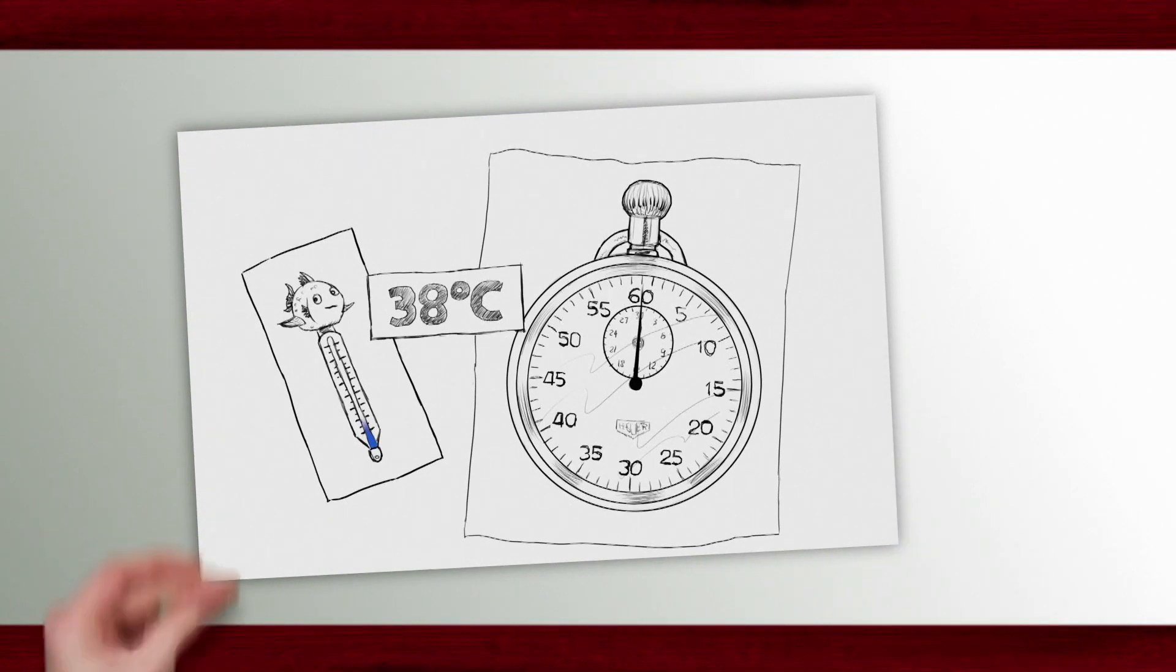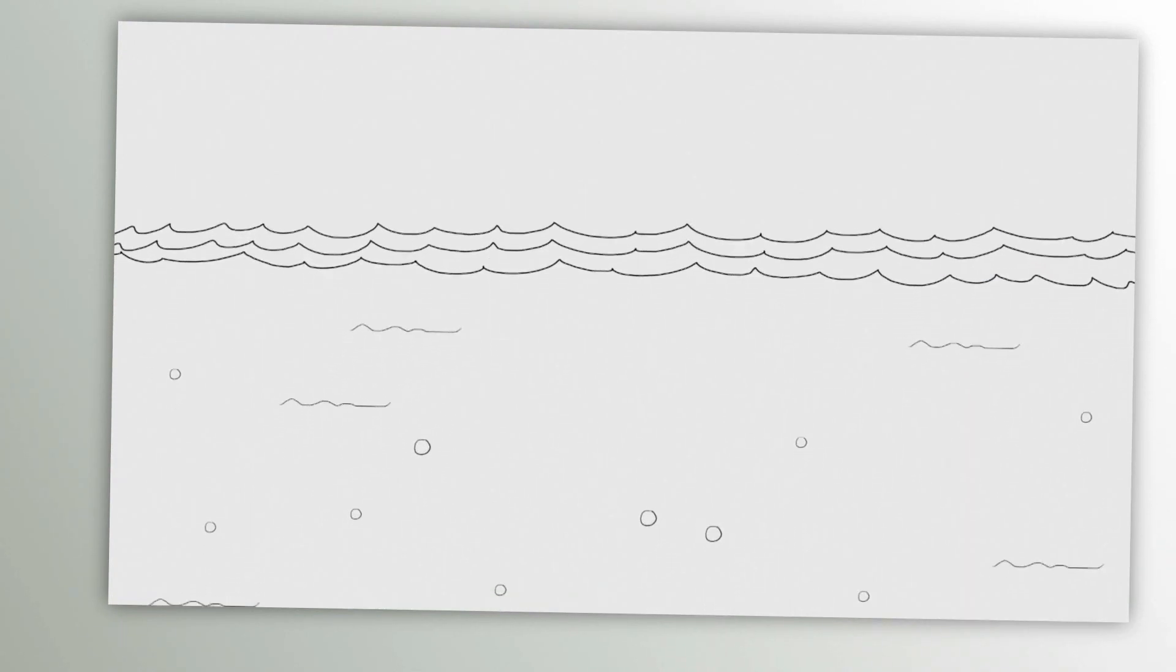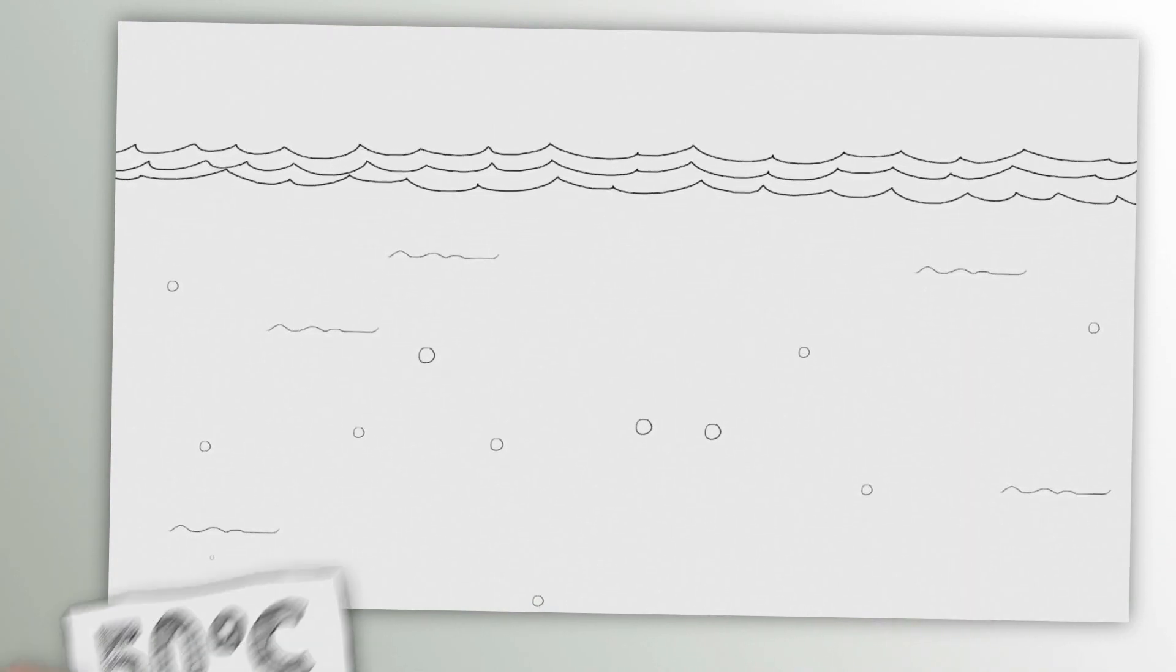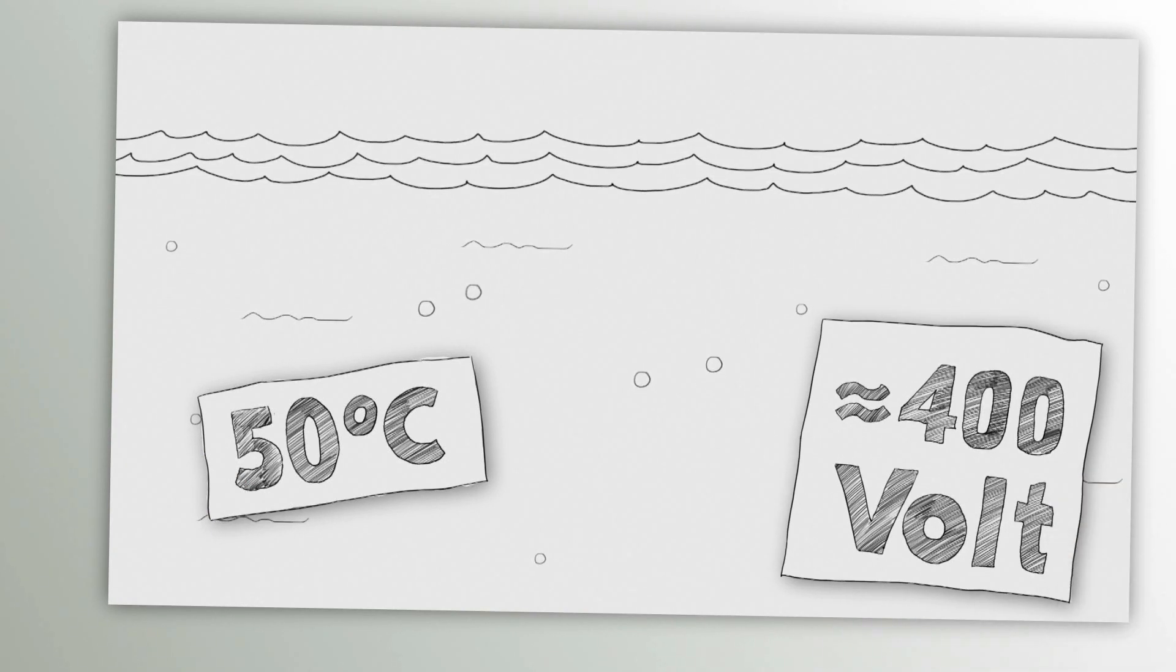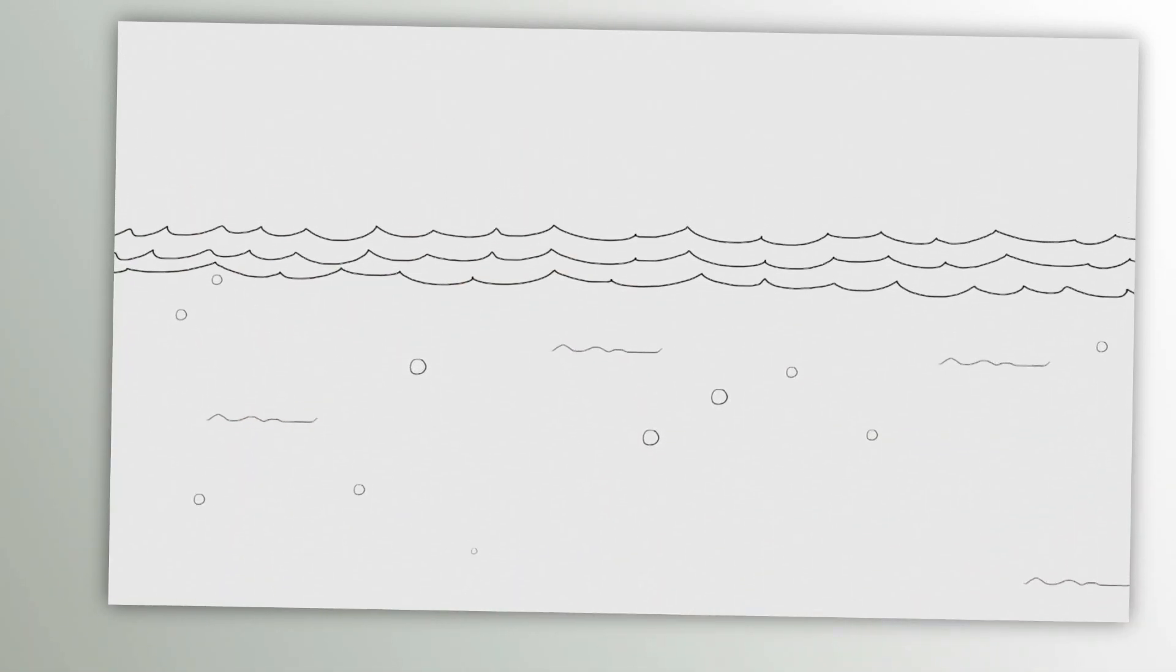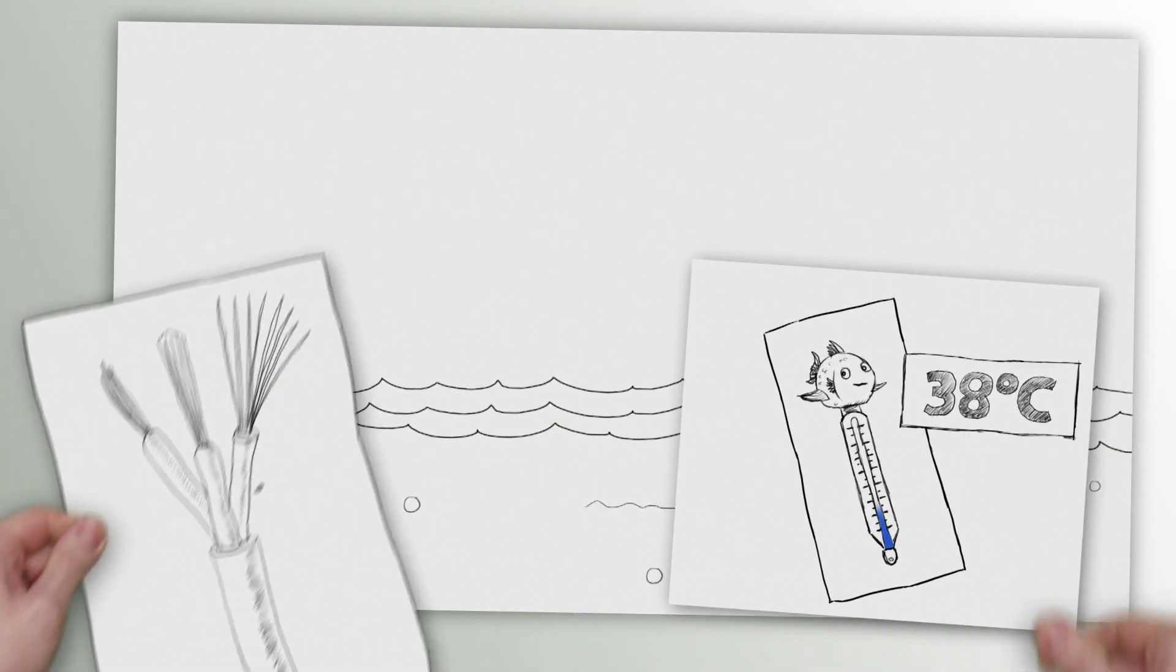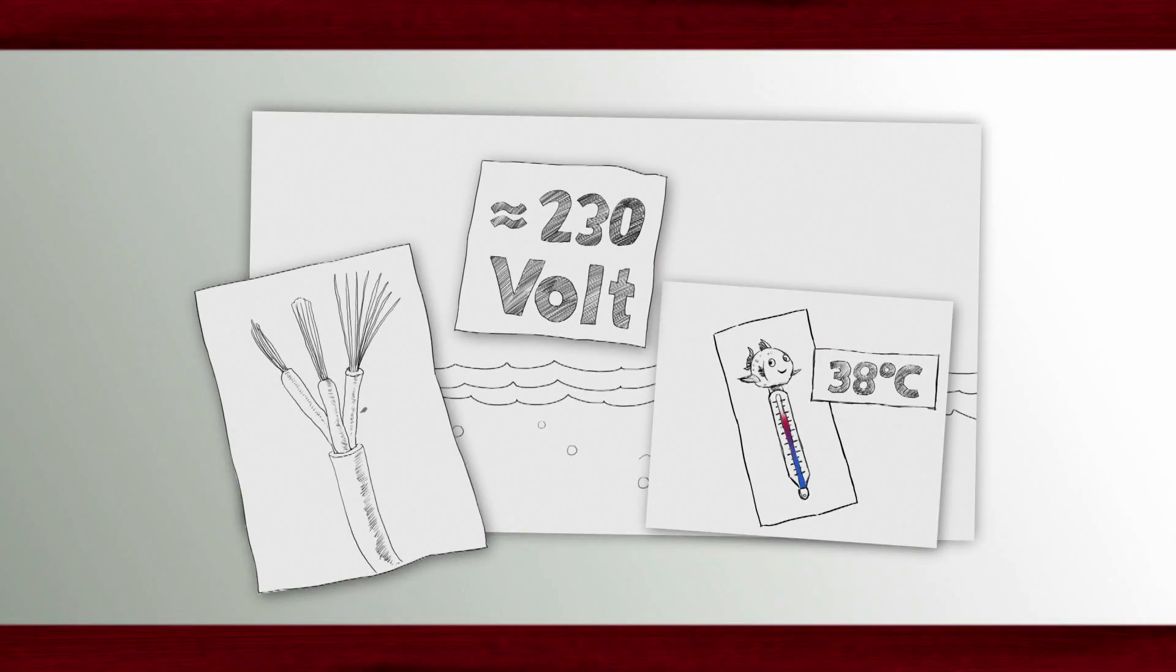Since instantaneous water heaters are based on the principle of heating water to the required temperature very quickly, these appliances need a lot of power for a short period of time. This is logical and explains why, when they have to produce large amounts of water, supply several draw-off points, or reach very high water temperatures, they run on 400 volts. Here, three-phase power is absolutely necessary. For small amounts and lesser temperature increases, 230 volt appliances and a single-phase power connection are sufficient.